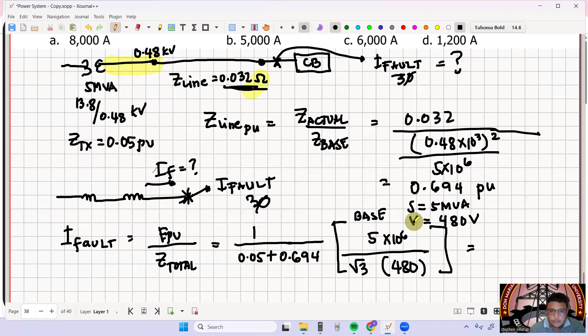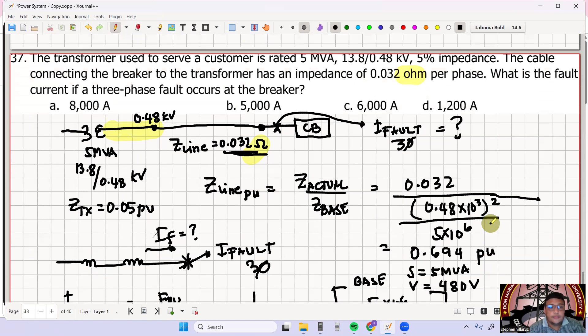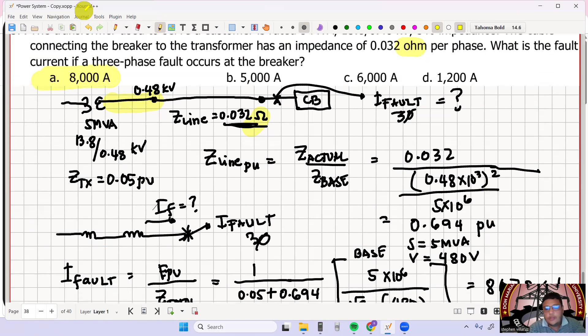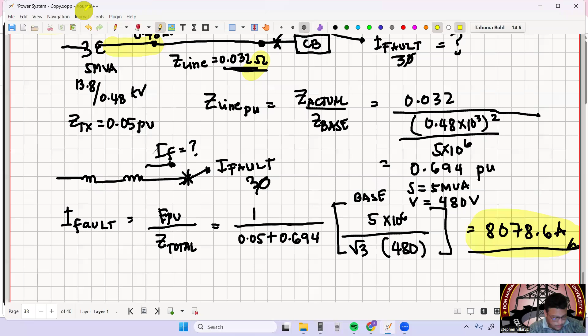So the base current is 5 mega over square root of 3 multiplied by 480. Therefore, it is 1 over 0.05 plus 0.694, multiplied by 5 mega over square root of 3 multiplied by 480, which is equal to 8,078.6 amperes, approximately letter A. That is what we design our breaker for, so that it does not surpass this 8,000.